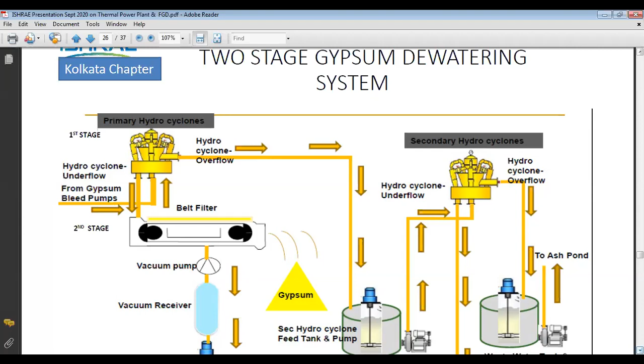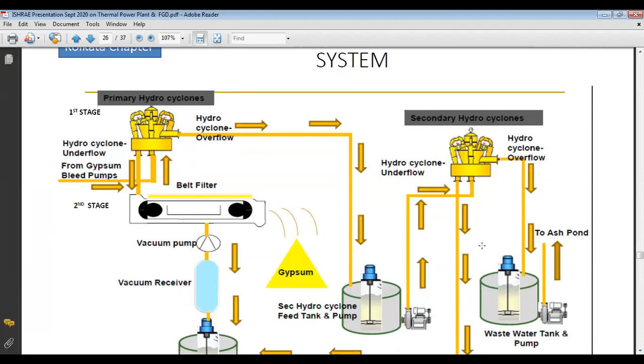There is a two-stage gypsum dewatering system: primary dewatering is the first stage, and this is the second stage. In the first stage, this is the primary hydrocyclone, and this is the vacuum belt filter, that is called the second stage. Normally, the gypsum is bled off from the absorber at 15 to 20% solid concentration, depending on the manufacturer also. So 15% solid is bled off, and it is fed to the hydrocyclone.